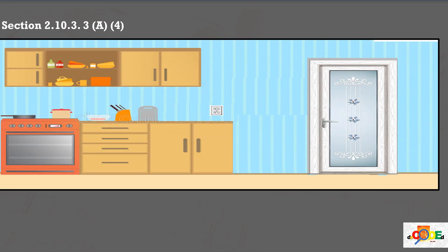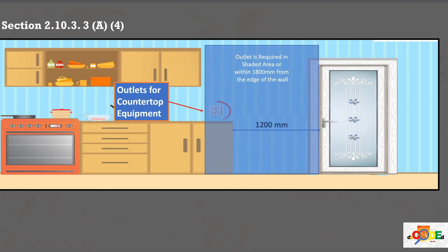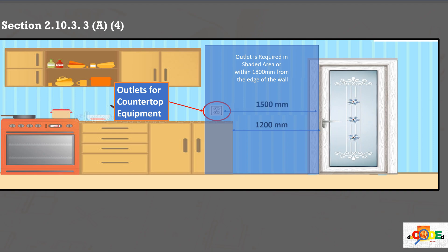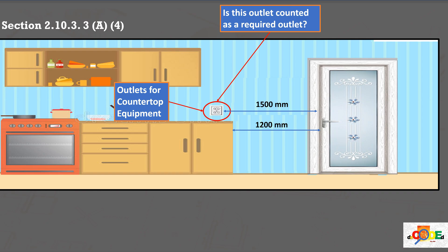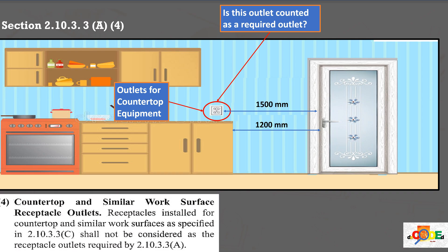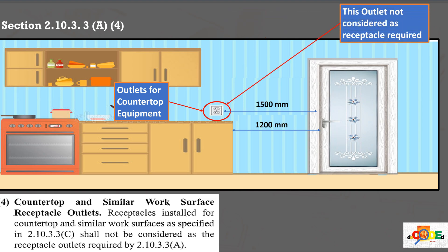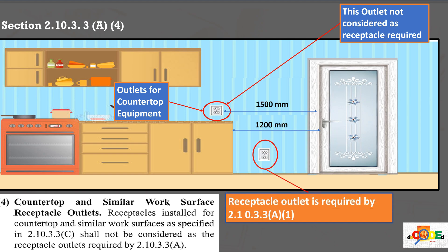In this example, the wall space is more than 600 mm, which means an outlet is required. However, there is an outlet in the countertop within 1,800 mm from the edge of the door. Is this outlet counted as a required outlet? In paragraph A4 of section 2.10.3.3, if an outlet is for countertops or work surfaces, even if within the spacing required in paragraph A1, this outlet is not considered to comply with the required outlet. Hence, an additional outlet within this area is required.